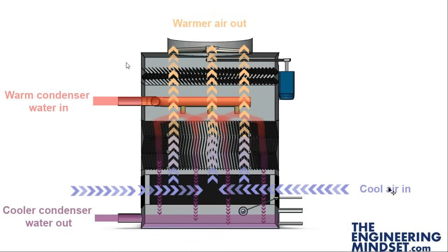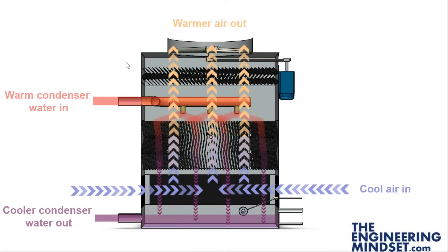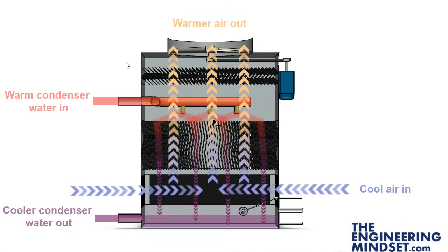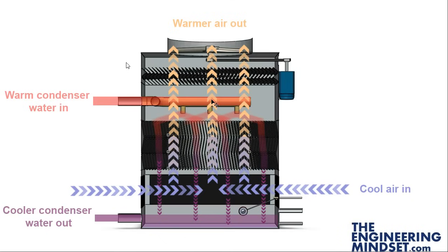Meanwhile, cooler ambient air is being sucked into this cooling tower and passes in the opposite direction of the condenser water. That picks up the heat from the water, but as it does that it'll also pick up some of the water making this air very humid and moist. So we've got this drift eliminator at the top here and that will condense some of that water so we can reclaim it and keep our operating costs down.